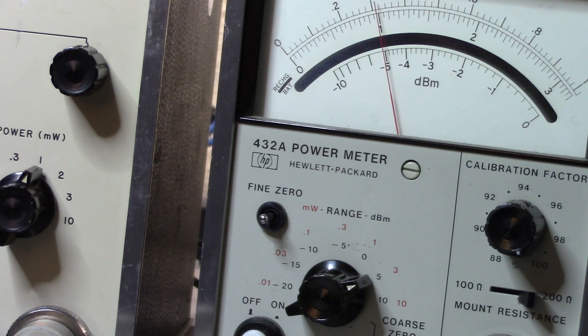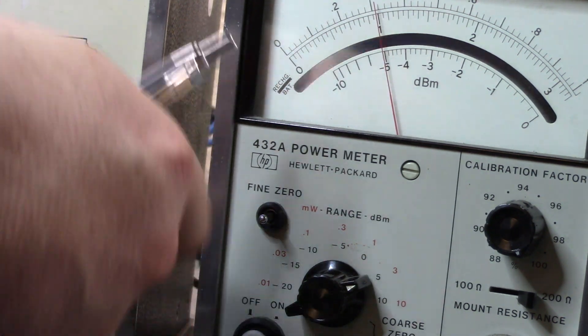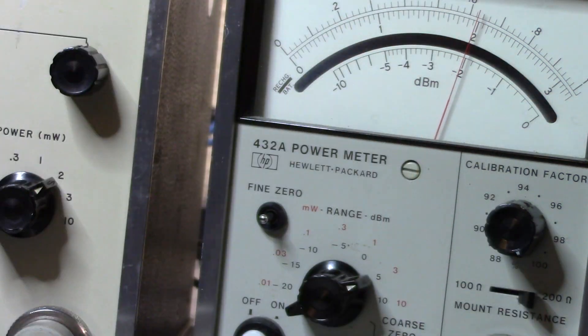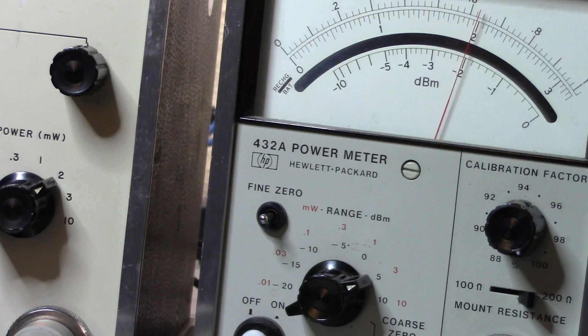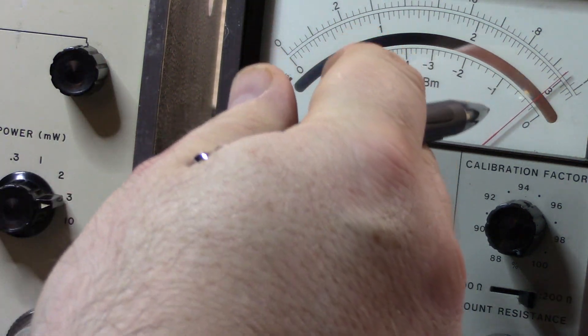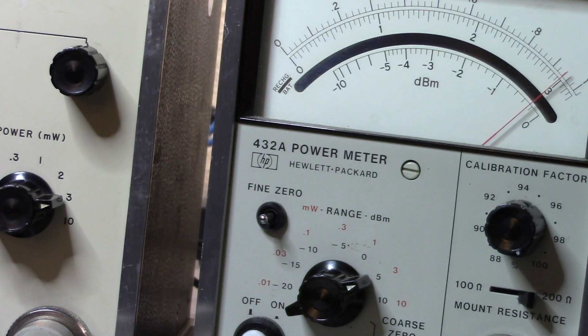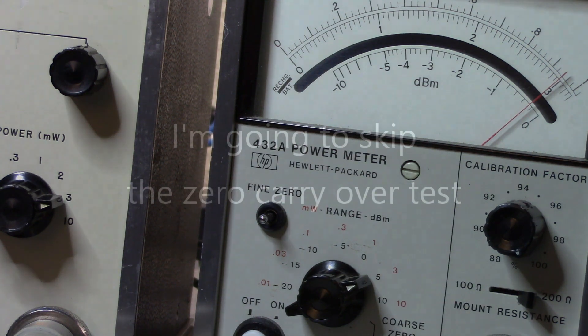Now we should be indicating one milliwatt and we're seeing one milliwatt there, so that's zero points off. When we go to two we should be seeing two and we're pretty damn close there at two, so I'll call that zero effectively as well. When we go to three we should see three and we're very close to three there as well. That's looking all good there.